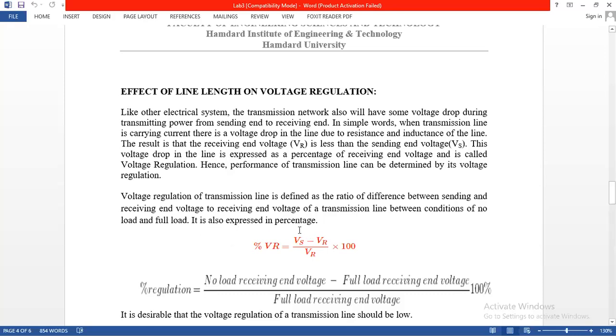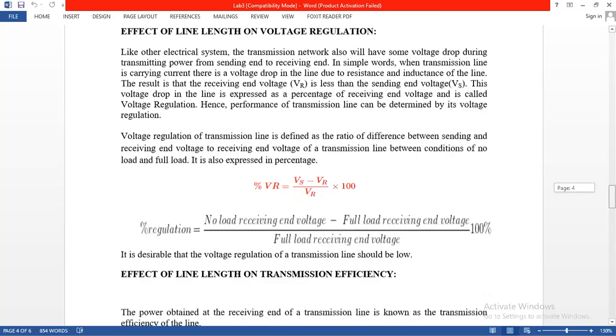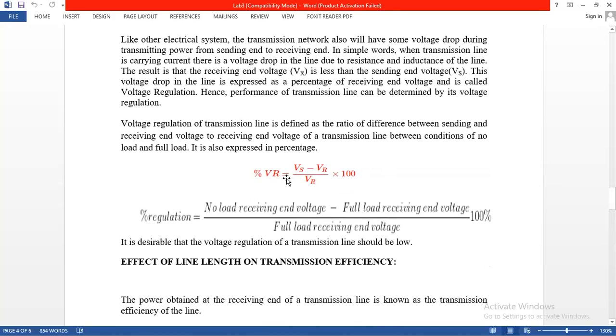It is expressed as percentage regulation, given by the formula: sending end voltage minus receiving end voltage, divided by the receiving end voltage, multiplied by 100. This gives us the percentage voltage regulation.